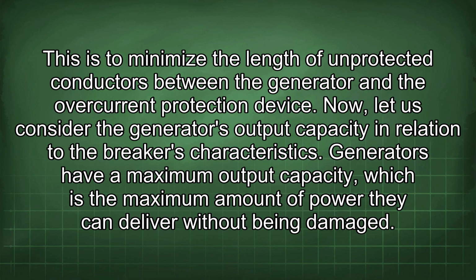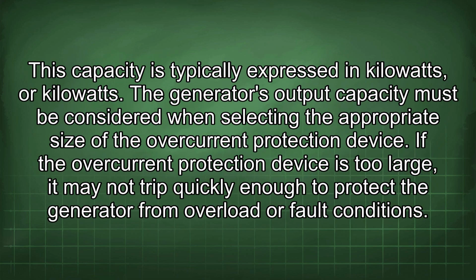Now, let us consider the generator's output capacity in relation to the breaker's characteristics. Generators have a maximum output capacity, which is the maximum amount of power they can deliver without being damaged. This capacity is typically expressed in kilowatts or kilovolt-amperes. The generator's output capacity must be considered when selecting the appropriate size of the overcurrent protection device.